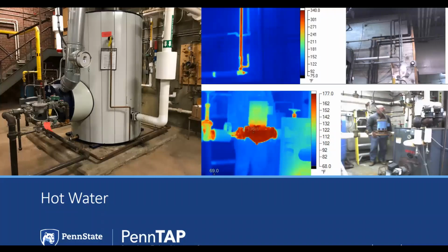For hot water systems, consider where the water is going and how long between uses. Are you heating up water for gym showers that's never being used? Do you have insulation on all your hot water piping? Using a thermal camera can give you a sense of what your hot water system is actually doing against your assumptions. Consider your space heating, domestic hot water, your kitchens, your insulation on your tanks and your lines. Look for any external leaks and for any internal leaks, such as steam traps, if this is applicable to your school or municipality. Also check to see if your equipment is ENERGY STAR rated and whether or not it might be a good idea to upgrade.